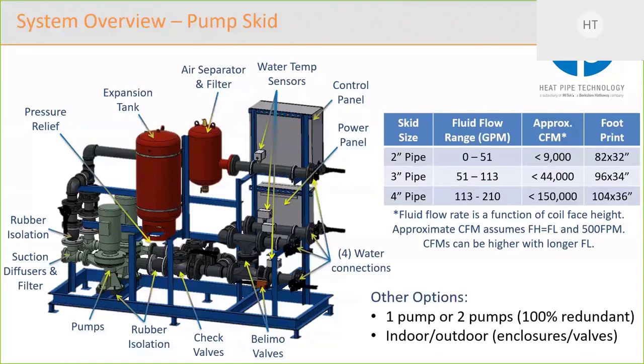So we showed two pumps. We do have a one pump option, although what we've seen is that customers have exclusively been interested in the two pump option. That gives the 100% redundancy. We also have indoor-outdoor options, and what that's really centered around is how the electrical enclosures are protected and the valves as well. There's a NEMA 4 enclosure that's available for the valves, and it's actually a different actuator that goes on there. So that would be an outdoor version.